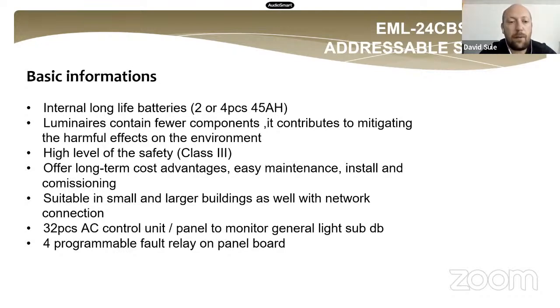This system is suitable for smaller and bigger projects too. It's a very compact system with 120 addressable units, and all of the light units have a unique ID, which is built inside the light driver. During the installation, there's no need to use any DIP switch or rotary setting for the address, because this ID is built into the driver.